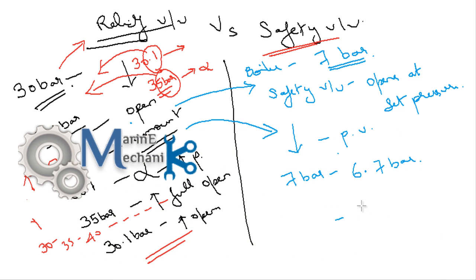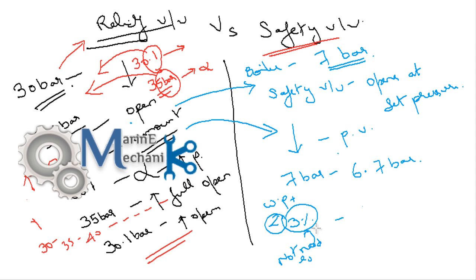As a thumb rule, safety valves should be set at no more than 3% above the working pressure — that is the maximum setting. The exact rule states the safety valve set pressure need not exceed 3% above working pressure. However, it recedes 4% below working pressure depending upon the design. For a 7 bar working pressure, 4% below that is approximately 6.72 bar, so that is the pressure at which it recedes.